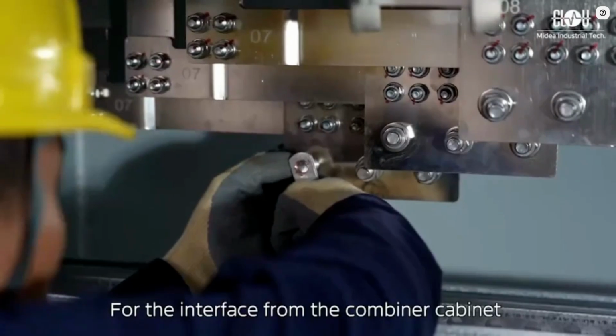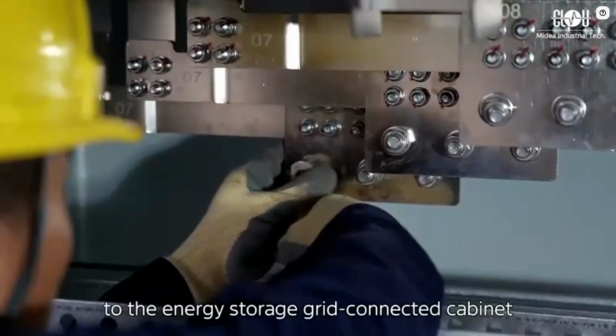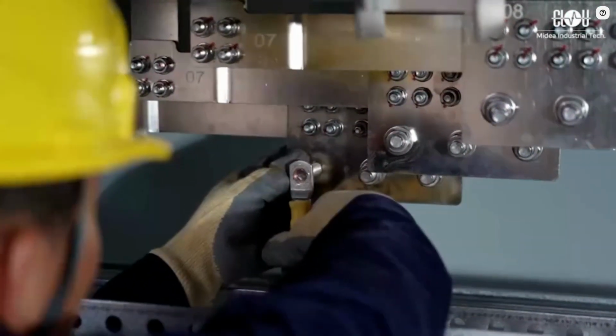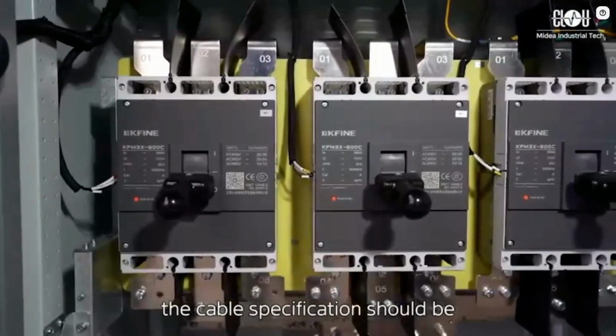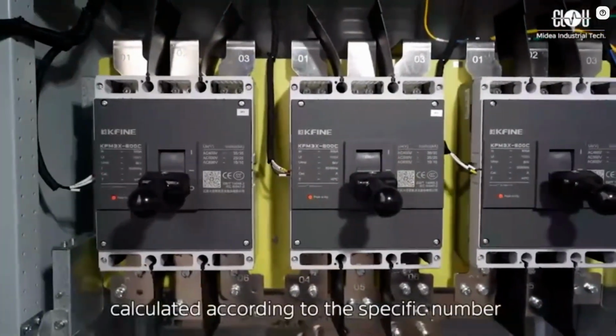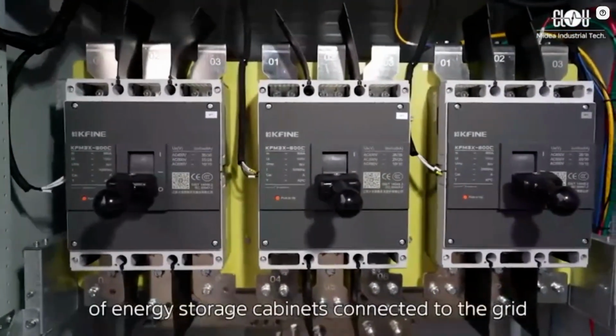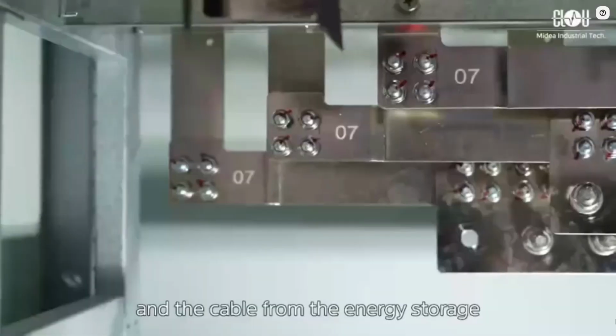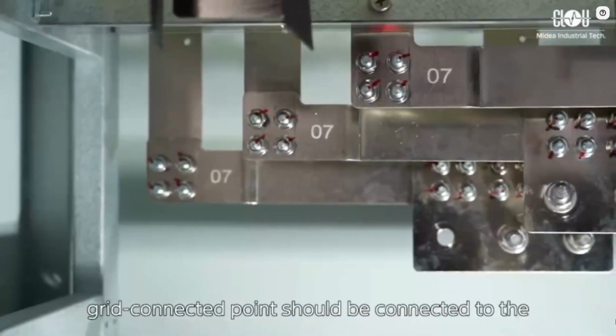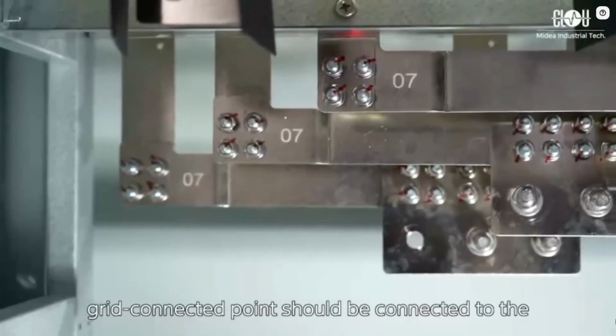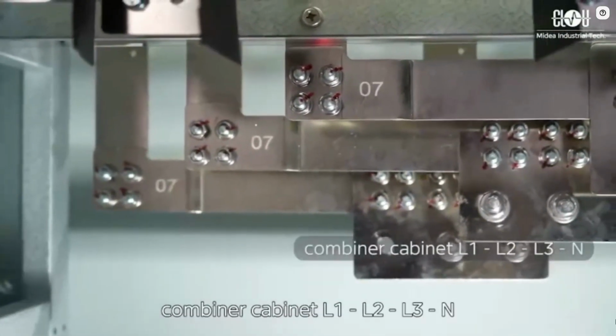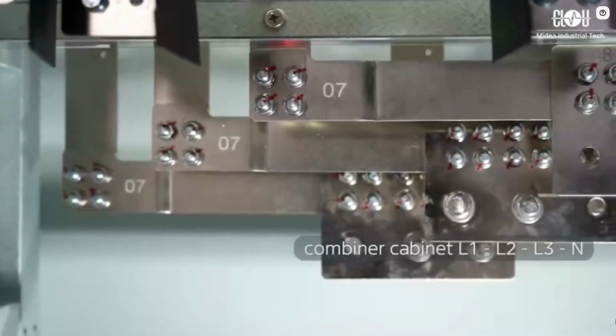For the interface from the combiner cabinet to the energy storage grid-connected cabinet, the cable specification should be calculated according to the specific number of energy storage cabinets connected to the grid, and the cable from the energy storage grid-connected point should be connected to the combiner cabinet L1, L2, L3, N.